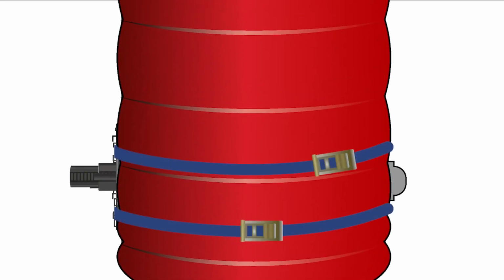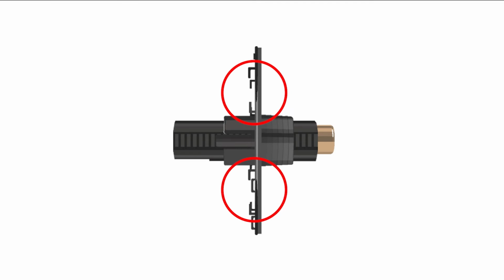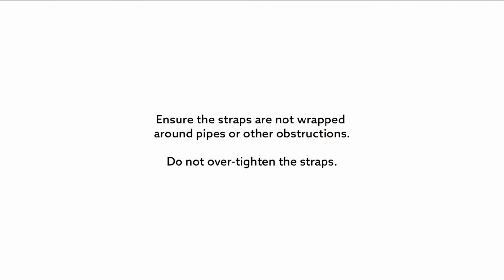If the tank has a padded jacket, use ratchet straps to secure the probes. Use the hooks on the flange to hold the straps in place. Fit the straps around the tank's body only, ensuring they are not wrapped around any pipes or other obstructions. Do not over-tighten the straps.